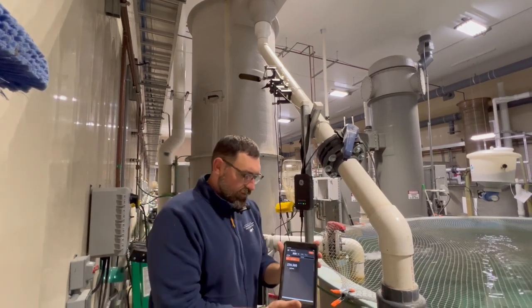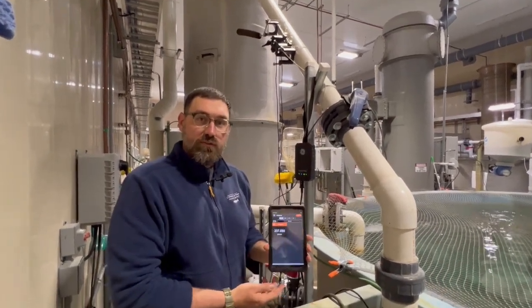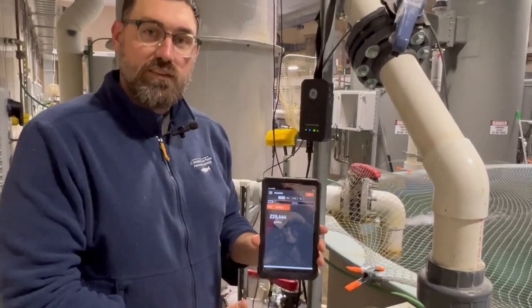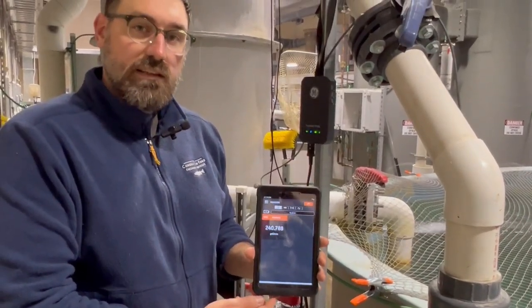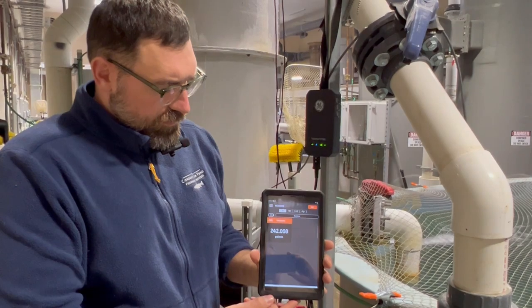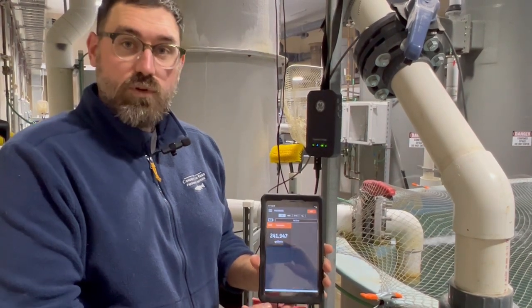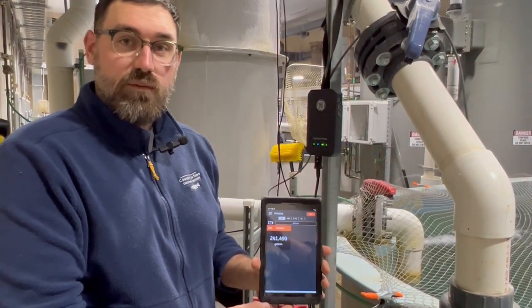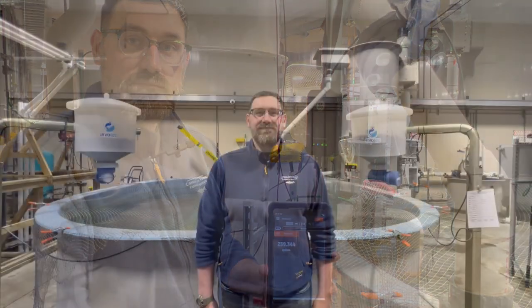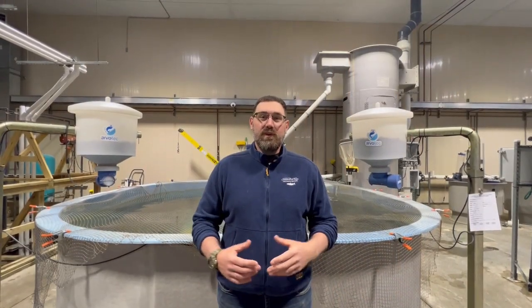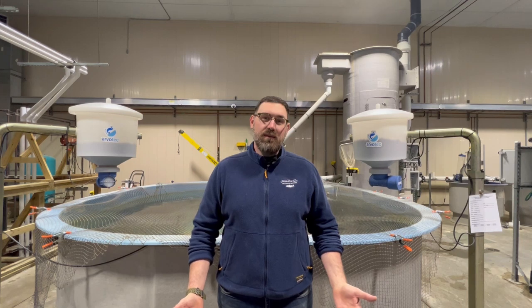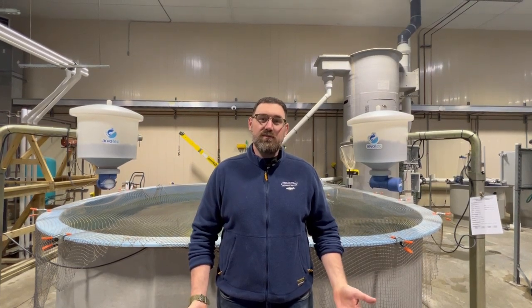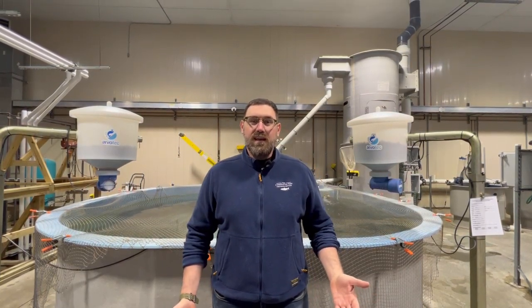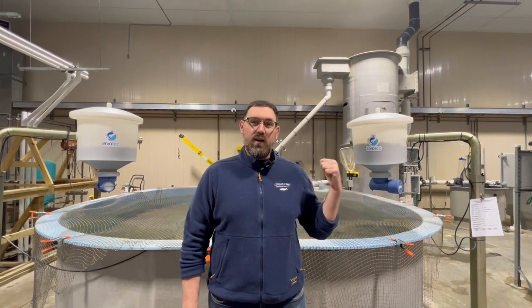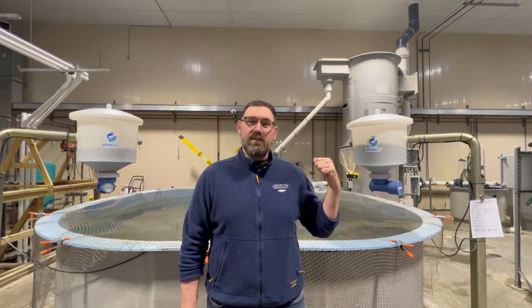And so we can see that we're actually producing a flow rate on this pipe, so everything's working fine. It looks like we're pumping 241 gallons a minute at this time. So we looked at what components make up an ultrasonic flow meter. We strapped it on the pipe and got a readout. And now we're going to take a look at a problem we have on the system behind us and try to troubleshoot it.